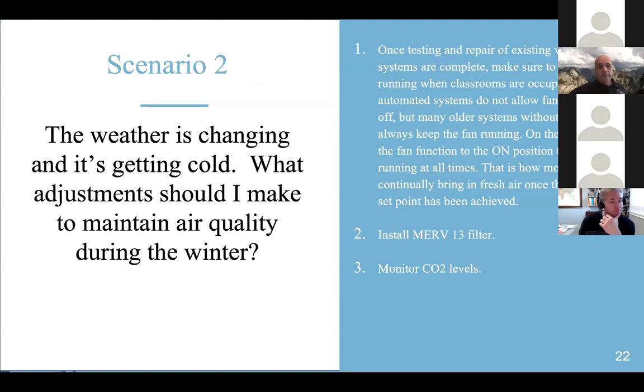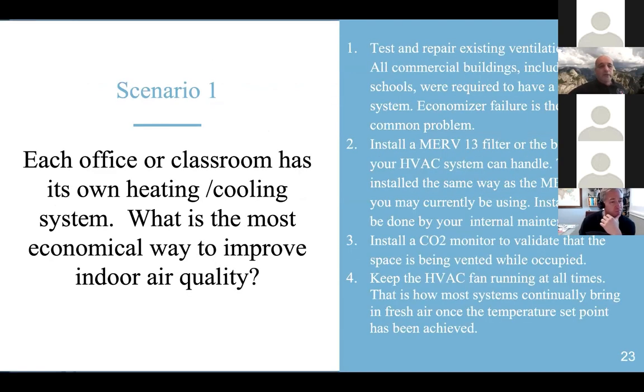So scenario number one: each office or classroom has its own heating and cooling system - what is the most economical way to improve air quality? First and foremost, test and validate the performance, making sure it's bringing in outside air. You want to install a MERV 13 filter, and then install a CO2 monitor to help validate that fresh air is coming in while the space is occupied.